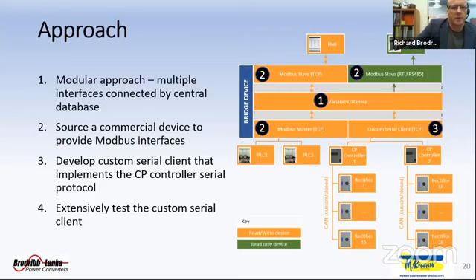Let's check in on a couple of key challenges we had with the serial implementation, which is probably no surprise to anyone who's done serial comms. There's a bit of a variation between what was documented in the OEM specs and the actual response of the serial interface. We resolved that through some degree of experimentation and reverse engineering, combined with support from the OEM to resolve any outstanding matters. The other issue was that essentially the CP controller sometimes became unresponsive when we provoked it. And by that, I mean, we scaled up from 4 rectifiers on the test bench to the 26 we had in the full build.